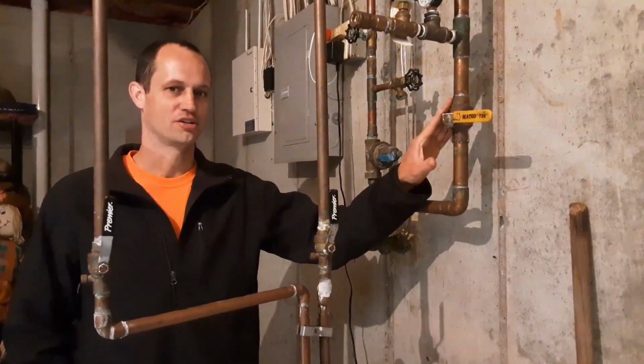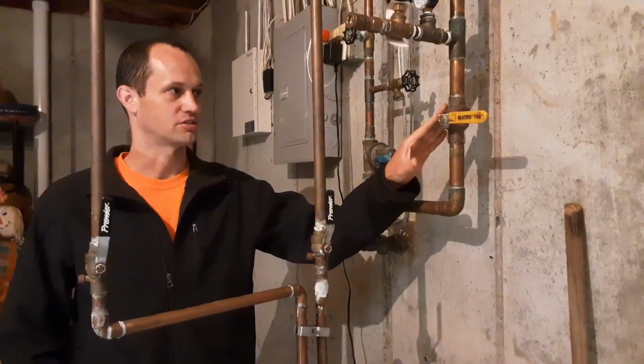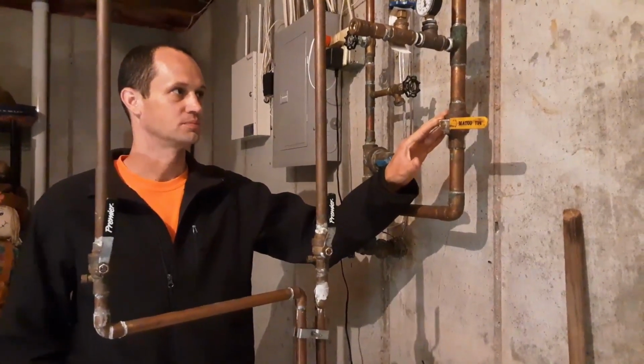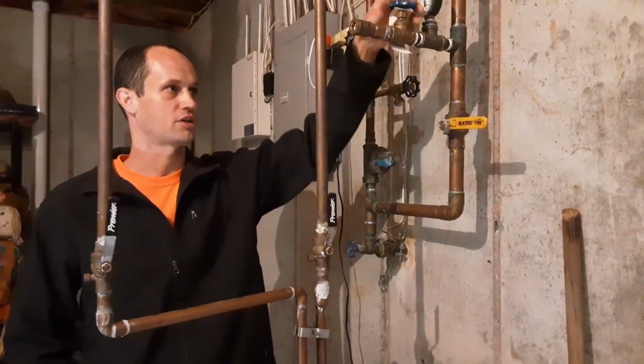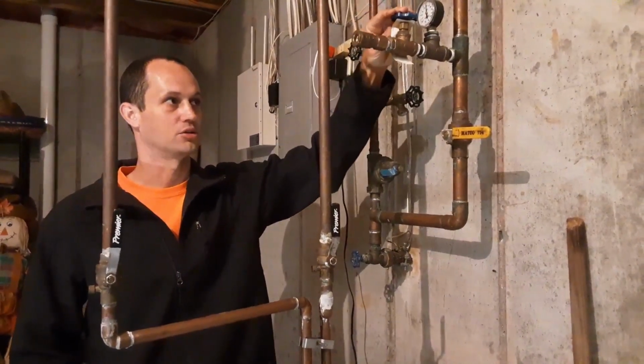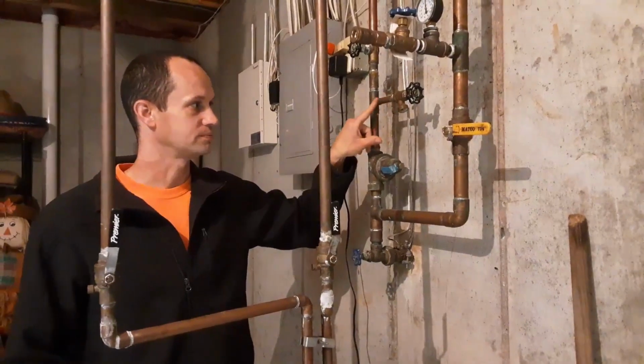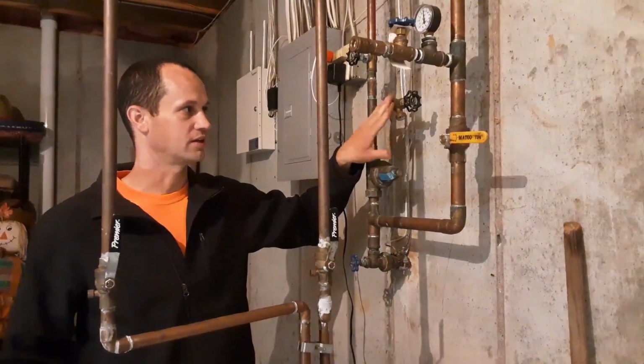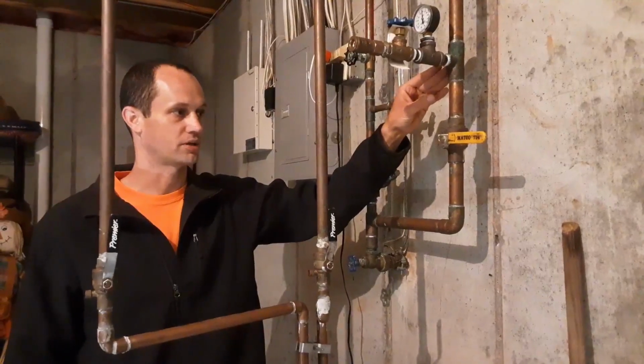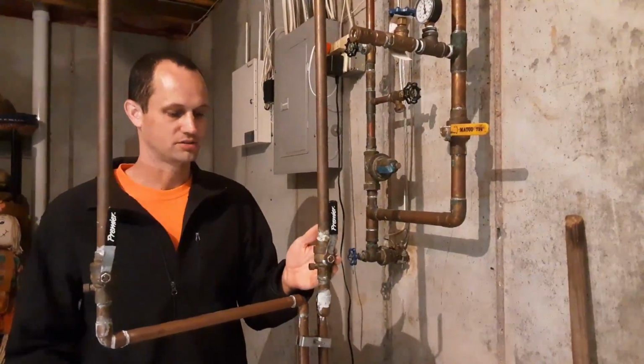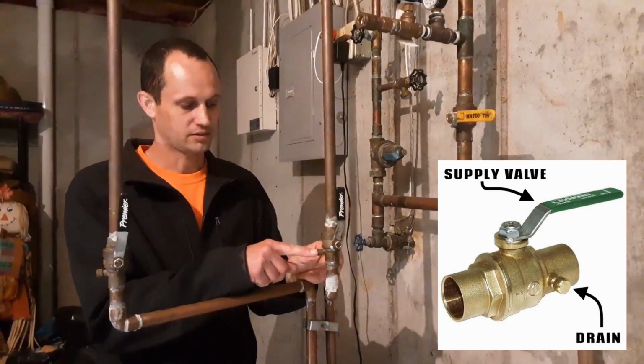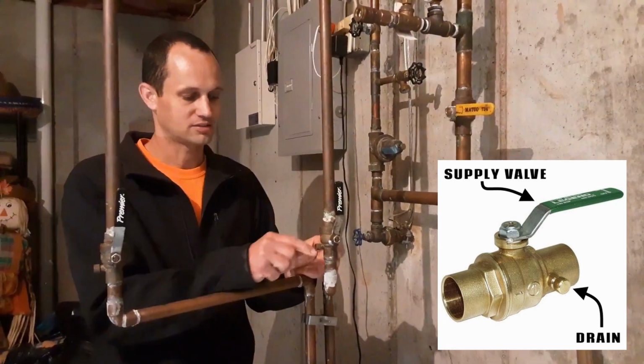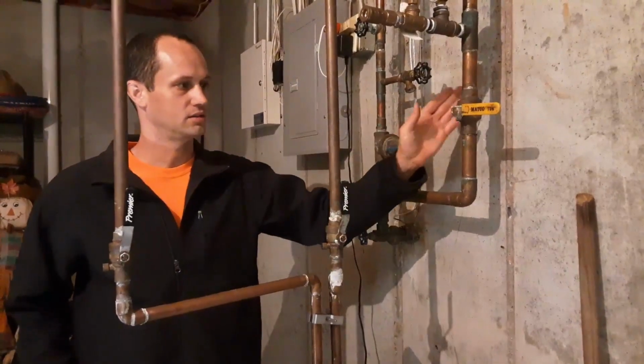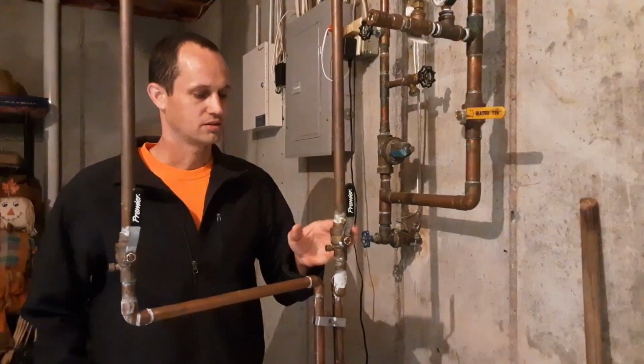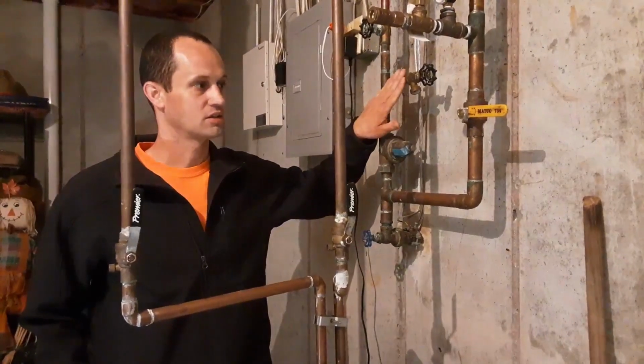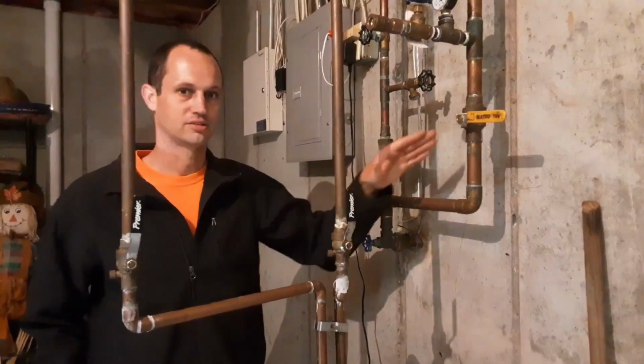So before we turn on your valve to your sprinkler system, we want to make sure that all the drains are closed. So in this particular application, here is the drain. So we want to make sure that this valve is tightly closed. It may also look like this one here. This is just a regular hose spigot. Again, this would be mounted right above the valve for the sprinkler system. And then here's the third style. This is a little drain for the sprinkler system. Make sure that this is tightly closed. In this particular example, this is not for the sprinkler system, and neither is this. But in your home, you may have any of those 3 systems.